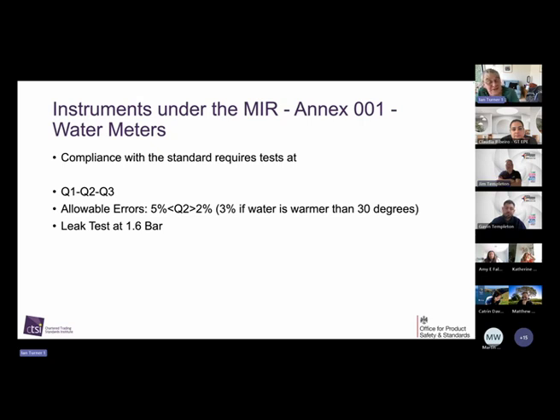And nowadays the technology has improved. I think last time I looked at these in any detail, the chambers are moulded, and the issue is the accuracy of the moulding, and they were getting them accurate and within tolerance, not just the metrological tolerance, but the actual engineering tolerance, to 99.8. Yeah, and you're thinking, wow. And that was sort of thousandths of a millimeter they were getting it accurate to. And so in the end, there's an interesting point of the story, it's about assessing the quality assurance. At the end of the day, if you're making the measuring chamber to that level of accuracy, putting water through it is kind of irrelevant. It's going to pass, isn't it?